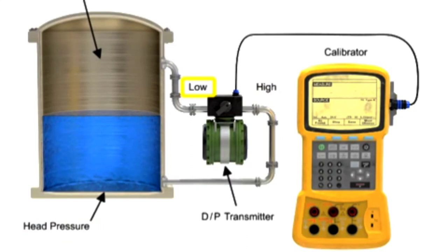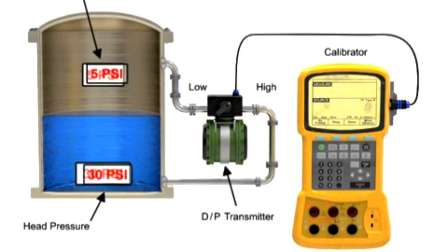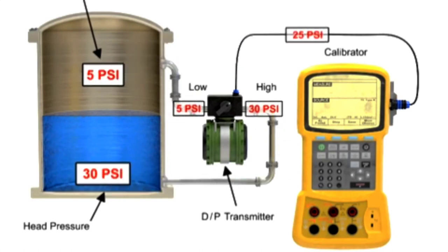The low-pressure input of the differential pressure transducer is connected to the vapor space pressure. The transducer subtracts the vapor pressure from the high pressure, resulting in a value that represents the hydrostatic head proportional to the liquid level.